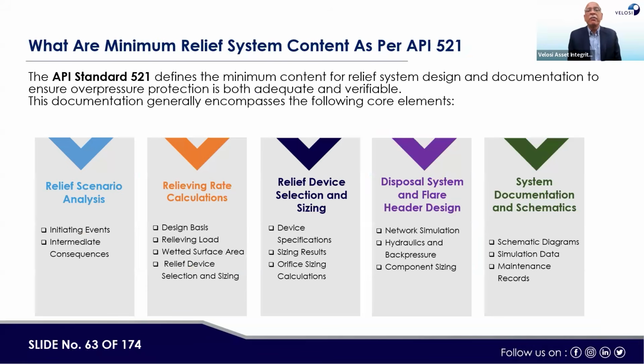Now, what are the minimum relief system contents? As such, this is just repetition, so you can get more information. Relief scenario analysis, like initiating events and intermediate consequences. Then relieving rate calculations, for example, design basis, relieving load, wet surface area, relief device selection and sizing. Relief device selection and sizing covers device specification, sizing results, and orifice sizing calculations. Then disposal system and flare header design, network simulation, hydraulic and back pressure, component sizing. Then system documentation and schematics, which are called P&IDs, PFDs, and other schematic diagrams, simultaneous simulation data, and maintenance records also kept in the system.